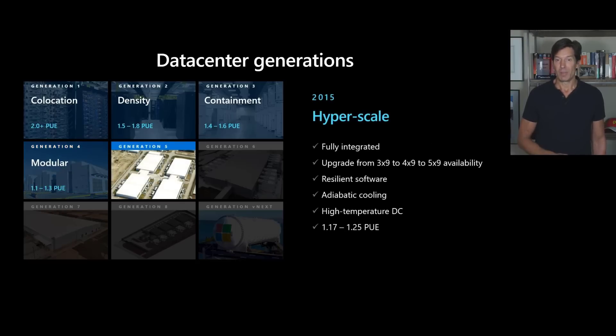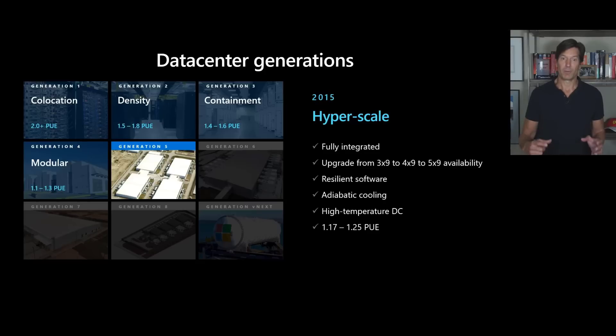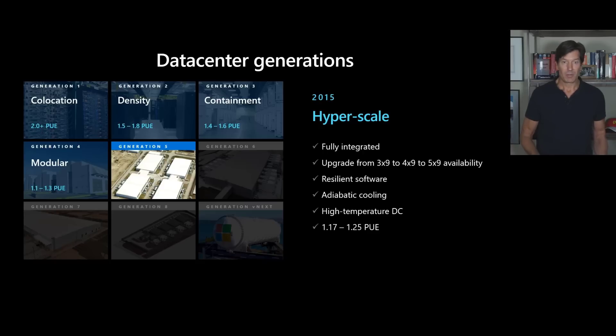Generation five was Microsoft's hyperscale phase. We were deploying so quickly around 2015 that we focused on how to get large footprints out quickly and grow them to meet hyperscale demand. You can see our DC 2015 design, which consisted of four eight-megawatt colo facilities with independent power, cooling, and network so each could serve as an independent availability zone. We initially made them in three-nines configuration, then upgraded to five-nines, delivering PUEs of 1.17 to 1.25.